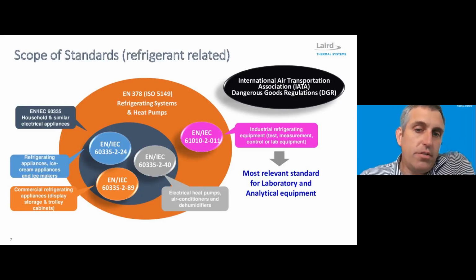So when we look at some of the standards that govern the use of refrigerants in products, there's a couple of different categories. One being whether or not this is a household type of appliance or some similar type of household appliance, and that all falls under this European norm, or EN, or IEC 60335. And so this governs a couple of different types of products, whether they be refrigerating products, displays, appliances, heat pumps. And then outside of that, there's within EN 61010, this is the laboratory safety standard for equipment used in the labs. And so this is more of an industrial type of application that has its own requirements around use of refrigerants in labs.